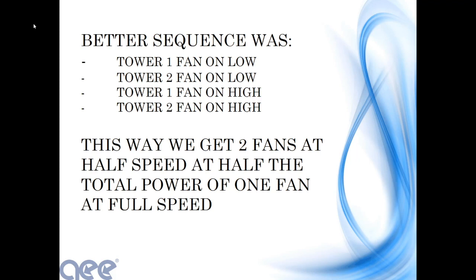Now, in fact, we only had 1 chiller online. It wasn't fully loaded, and roughly the tower and the chillers were equal size. What would actually happen in this scenario is the lead tower would come on low, and the lag tower would cycle on and off at low speed. But even if it was running constantly, we're only using half the power.